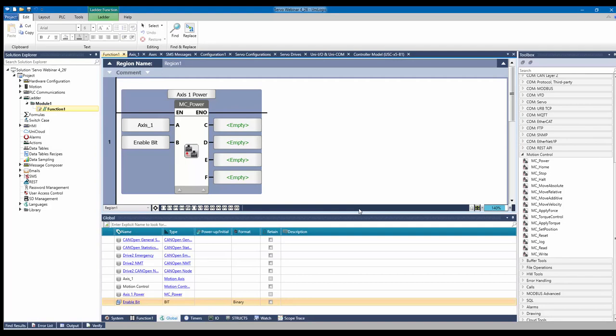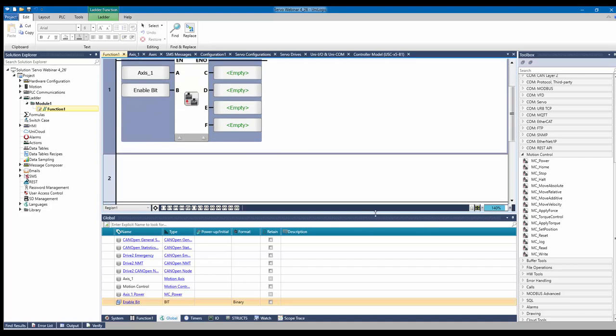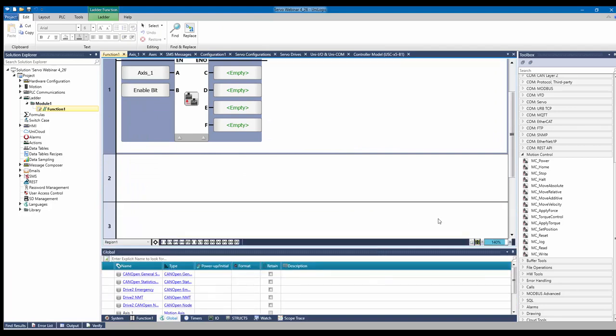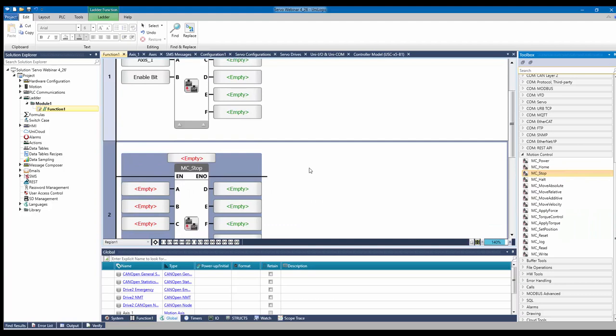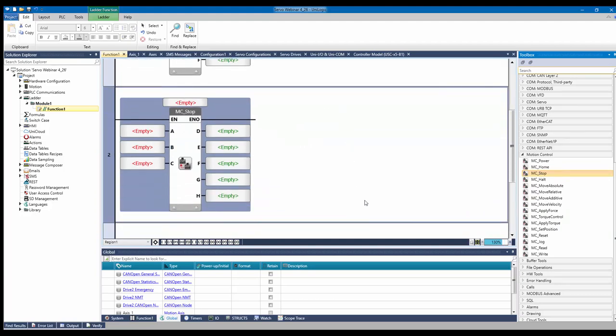The MC Power is the initial connection from the PLC to the drive — it's the broadcast message indicating the PLC has control over this axis. Next, I'm going to grab another function block — MC Stop. This function block, when triggered, is going to stop the drive in its tracks. Whether it's in the middle of a move or an emergency condition happens, you can trigger MC Stop for that.